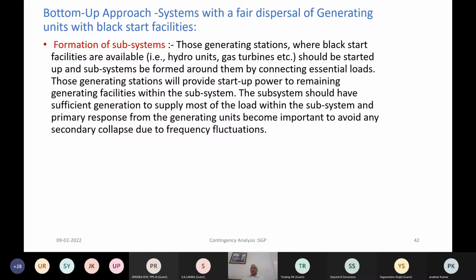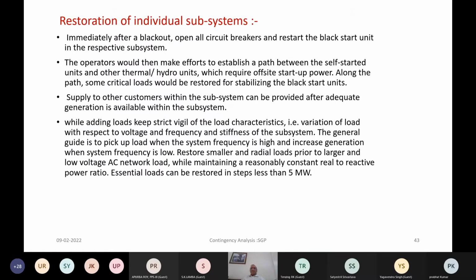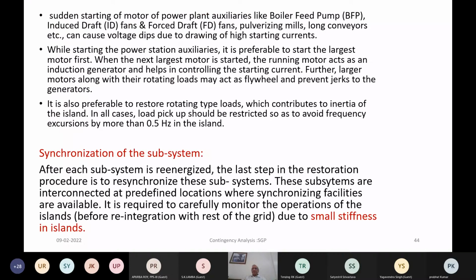That means you start from the small unit energizing local loads, and then a number of subsystems which are in service take load in their own subsystem, and then they connect with each other, form a bigger system and slowly expand the system. So this is the restoration of the subsystem. And then synchronization of the subsystems, as I mentioned.